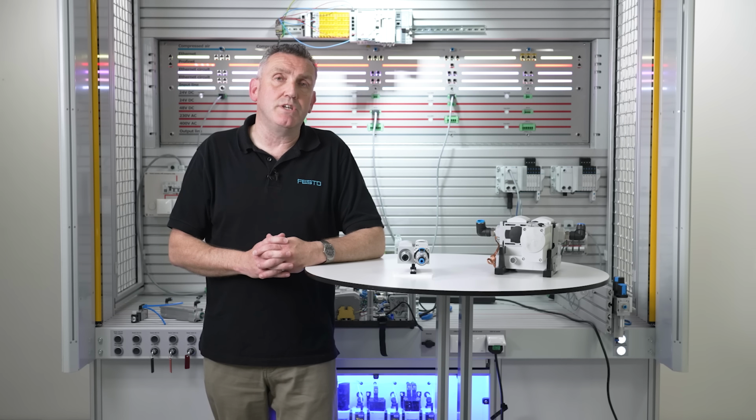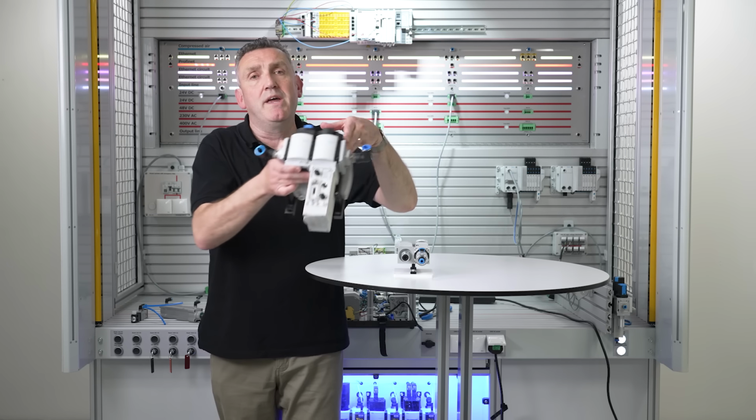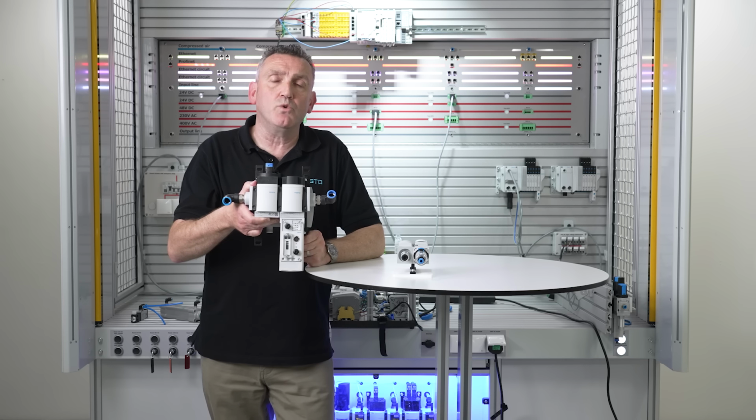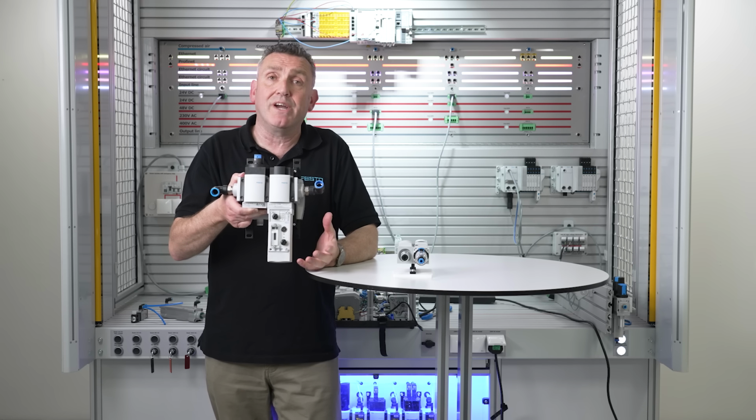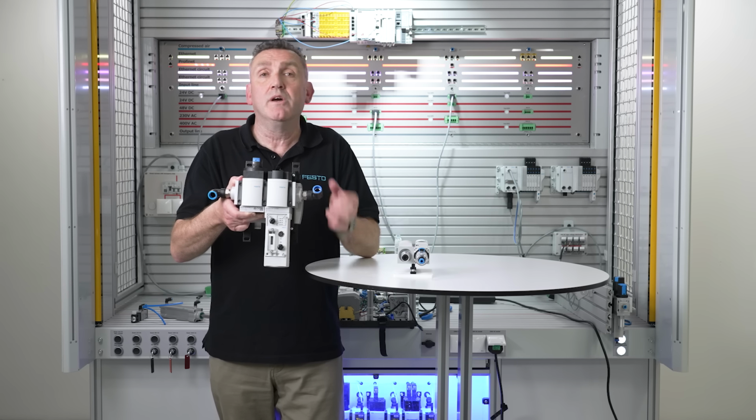It's even possible to use an intelligent device such as the E2M energy efficiency module, which will automatically detect when the machine is idling or not producing and will turn the air on and off for you without any manual intervention. Before doing this though, it is important to audit the machine to see if there are any vertical axes or pneumatic clamps that when we reduce the air may cause an unsafe condition or give us problems in restarting the machine when we re-establish the air to it.